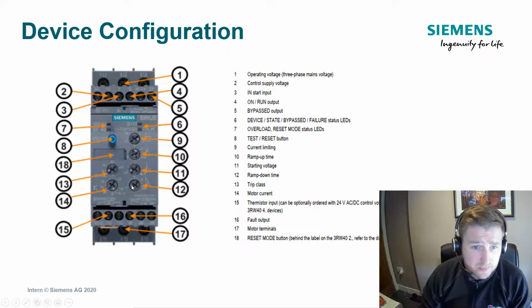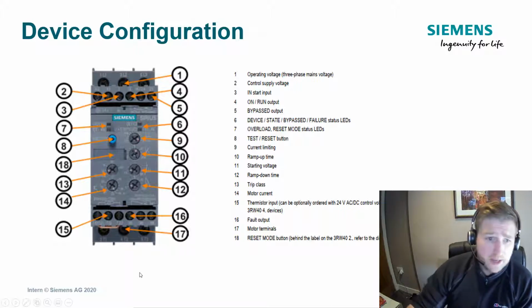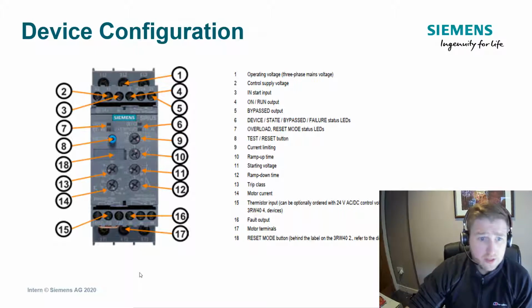And then this last pot here is for the ramp down time. So when either of these three terminals, the voltage has been removed or the signal's been removed, then the device will coast down to 0 RPM in the time allocated here, and it's similar to the ramp up time here, so it goes from 0 to 20 seconds. In this terminal here, as you can see, terminal 15, that is where you can have an evaluation of a thermistor module which is connected to the motor windings. So it has an inbuilt thermistor function, but only on certain configurations of the 3RW40 is that an option.